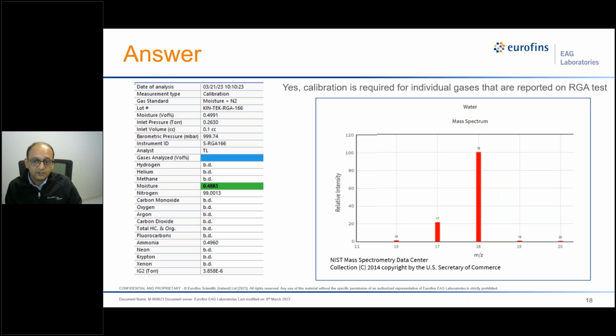So for hydrogen, we use a hydrogen and nitrogen mix, and we acquire the gas standards from third party certified gas standards to do that. And we do this calibration quarterly or as and when required. If we see that the hydrogen or some other gases are not at the expected values as considered by the client or considered by some other implications, then we would definitely calibrate the system on the same day using the standard gas. Ideally, they are required to calibrate every quarter.